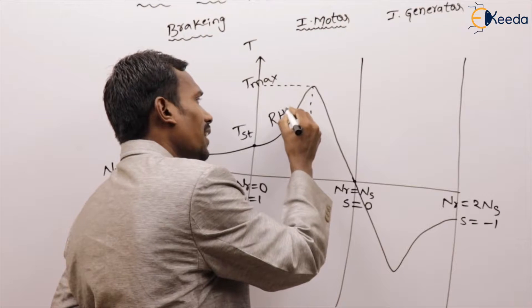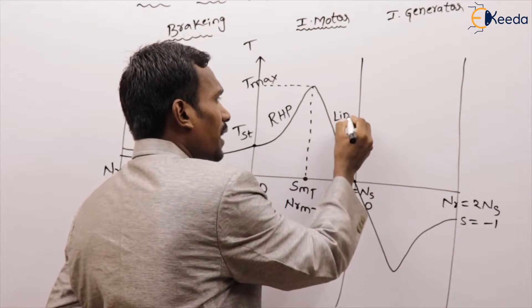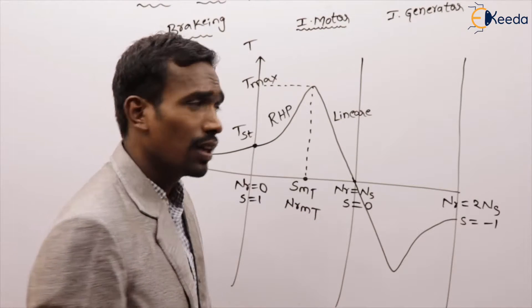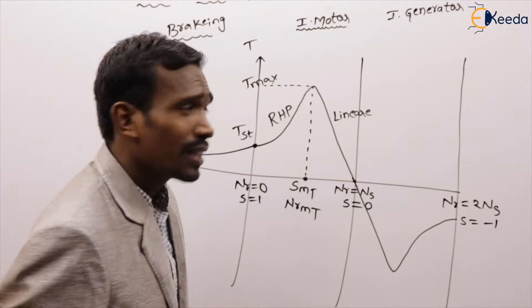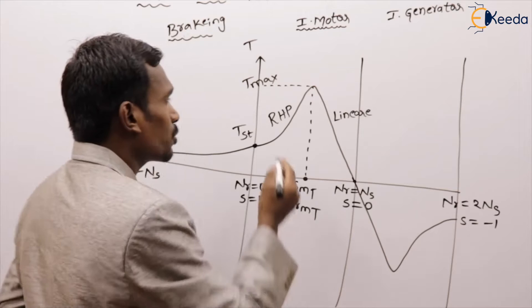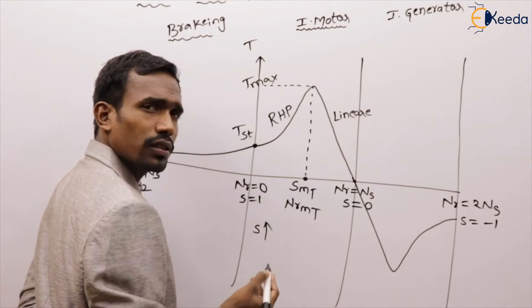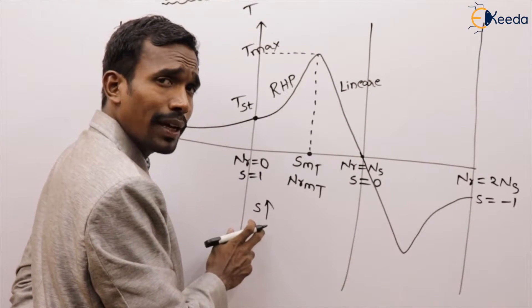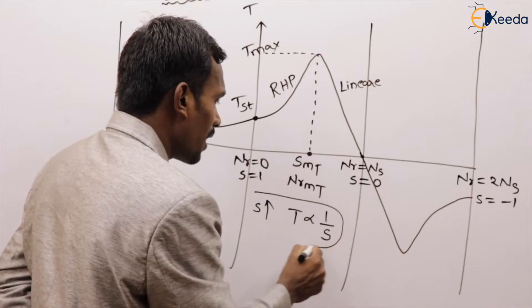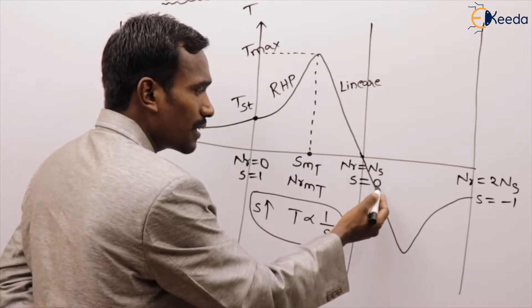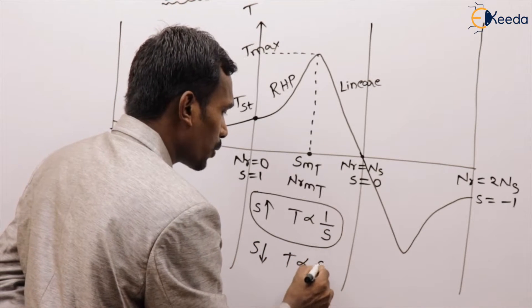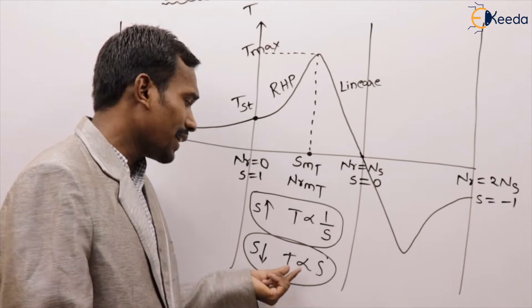The torque-slip curve is nonlinear. The nonlinear portion is a rectangular hyperbola, while the other portion is a linear curve. At high slip values, torque is inversely proportional to slip. At low slip values (near synchronous speed), torque is directly proportional to slip.